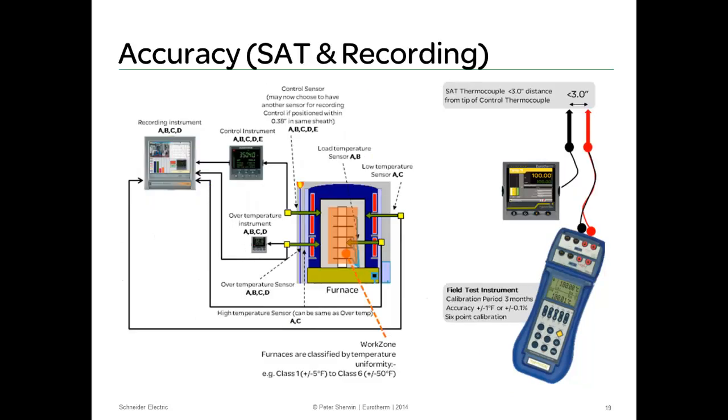Another smart way to ensure the controller and recorder read the exact same temperature and helping SAT results is to take advantage of digital retransmission available in the higher precision controllers. What you see on the controller is what you capture on the recorder. No slight deviations due to non-digital retransmission, separate thermocouples or scaling issues.